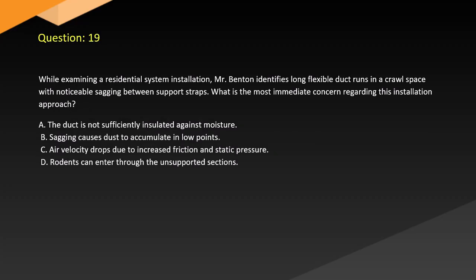Question 19. While examining a residential system installation, Mr. Benton identifies long flexible duct runs in a crawl space with noticeable sagging between support straps. What is the most immediate concern regarding this installation approach? A. The duct is not sufficiently insulated against moisture. B. Sagging causes dust to accumulate in low points. C. Air velocity drops due to increased friction and static pressure. D. Rodents can enter through the unsupported sections.